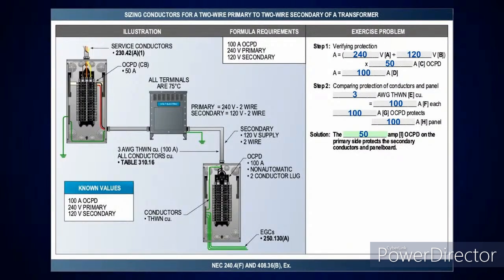Now this one is looking where you've got a 2-wire primary to a 2-wire secondary of a transformer, and this is just confirming what we have up there. So I have an upstream overcurrent device of 50 amps, okay, and we're showing you the downstream at the panel from the transformer is 100 amps, and we're telling you we're running number 3 THWN.